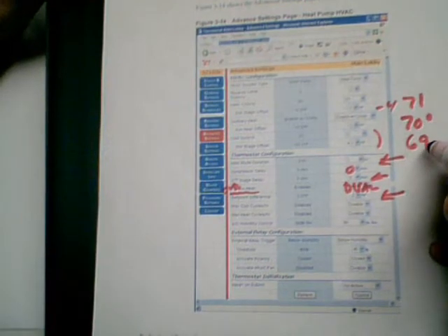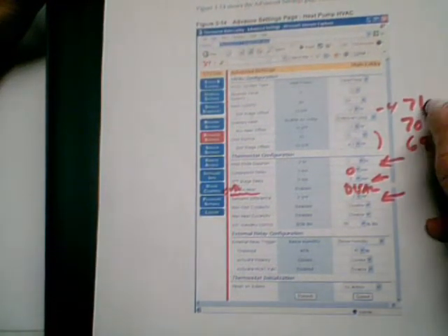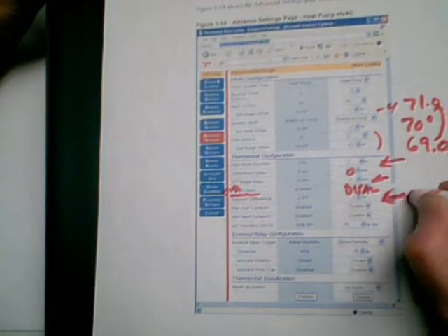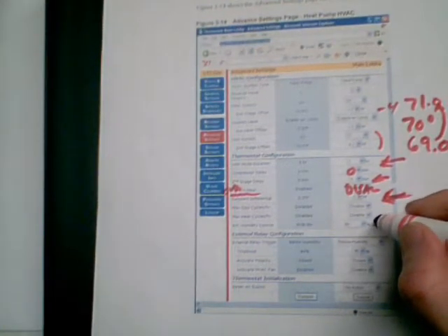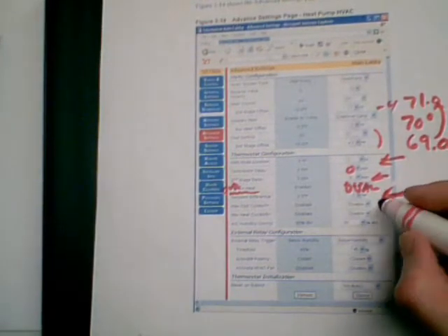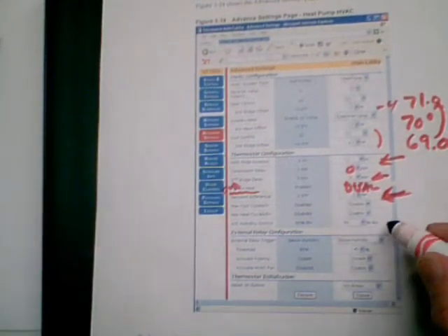So it's going to wait till it drops down to 69.0, and then it'll turn the heat on until it hits 71.0. So it's going to play back and forth. And 2 degrees is typically considered, I think, by most engineers, a good setting, and that's what was recommended to us. But that certainly can be changed. Maximum cool and maximum heat cycles per hour. Probably not terribly applicable, although we have used that for the...